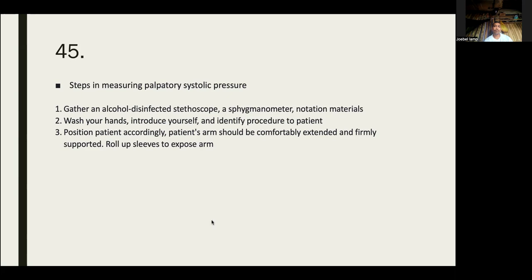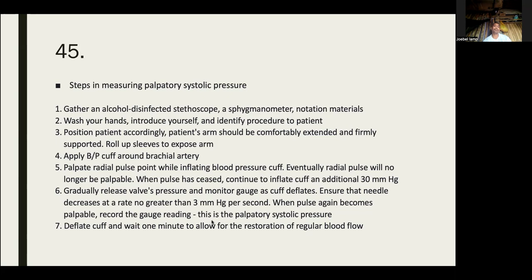Palpate the radial pulse point while inflating the blood pressure cuff. Eventually, the radial pulse will no longer be palpable, no? When the pulse has ceased, continue to inflate the cuff an additional 30. Gradually release the valve's pressure and monitor the gauge as the cuff deflates. Ensure that the needle decreases at a rate no greater than 3 millimeters mercury per second. When the pulse again becomes palpable, record the gauge reading. This is your palpatory systolic pressure. Deflate the cuff and wait 1 minute to allow for the restoration of regular blood flow.